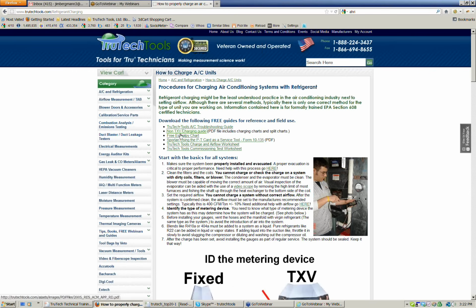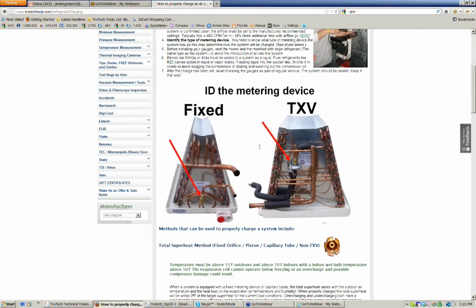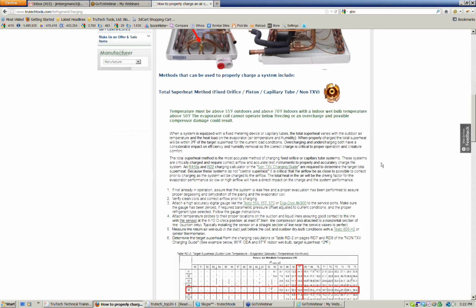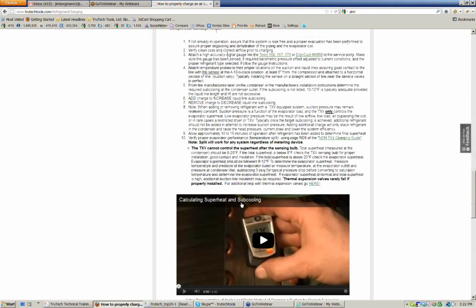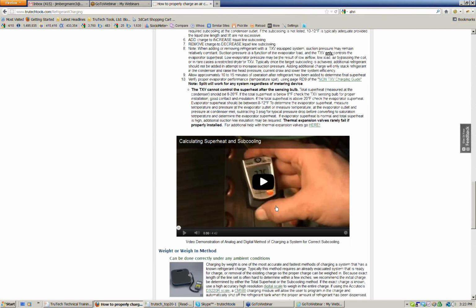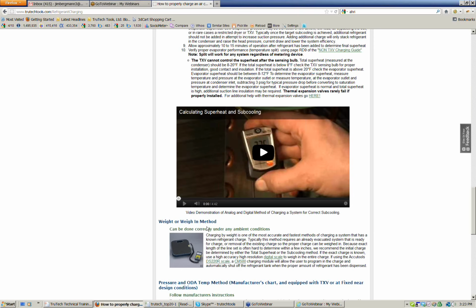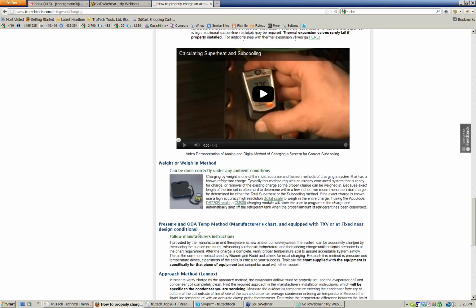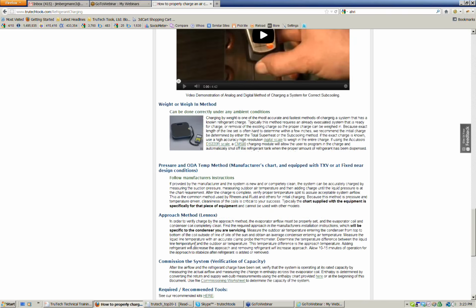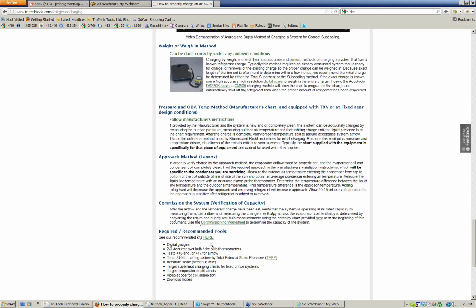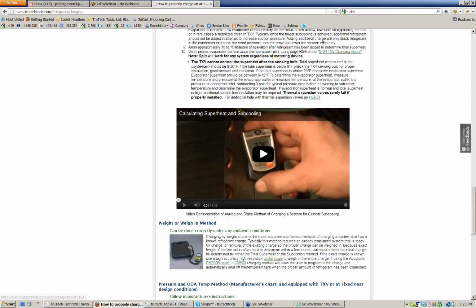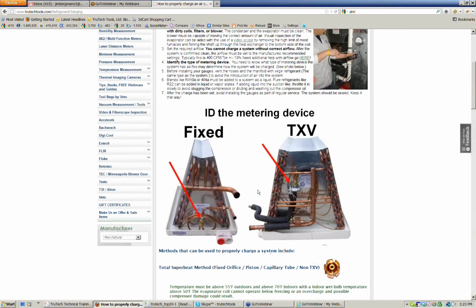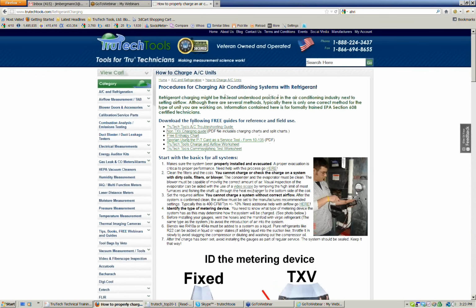There's a troubleshooting guide, an enthalpy chart, how to use the pressure temperature chart as a tool, some guides on airflow and commissioning worksheets, and I've outlined the process step by step on how to charge a system, how to use the charts, some notes on subcooling that go into more detail, a little video of how to do that process, some notes on the weigh-in method and approach in commissioning the system, verification of capacity, and some of the required tools. If you go into some of these content pages, you'll find a lot of great information on how to properly charge a system.